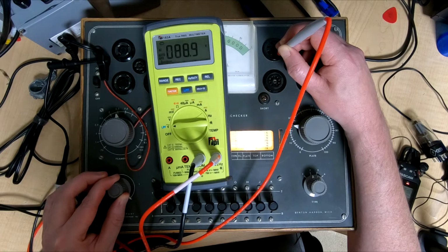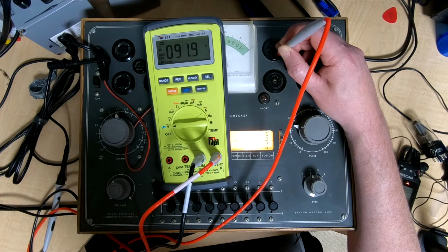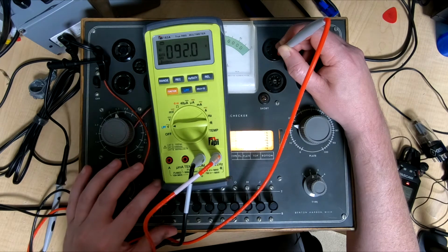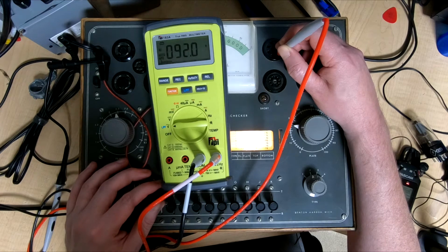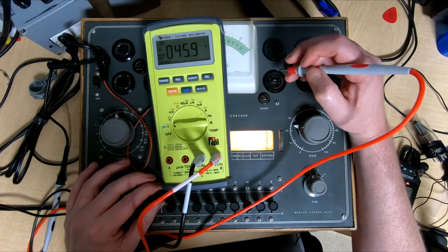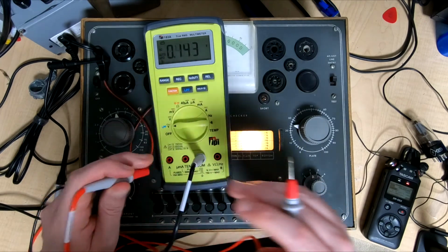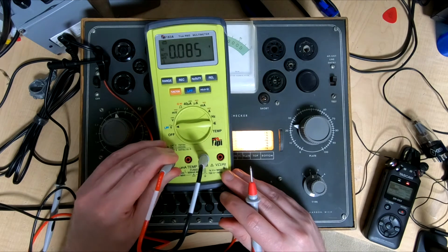So basically the theory of operation is that it warms the tube up, applies voltage to the plate, and checks to see that there's a current running that the meter then shows. There is also a short detect on the device, which checks to see if the plate voltage is shorted either to filament pins or ground pins.